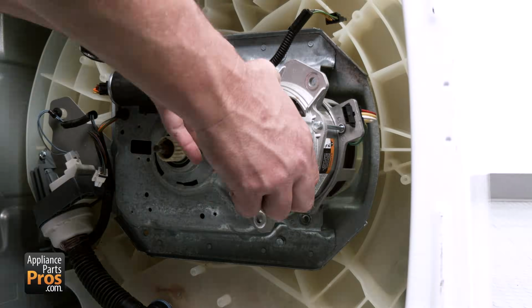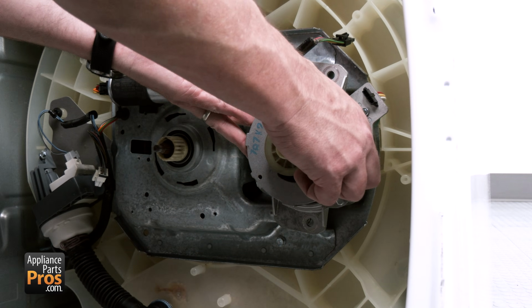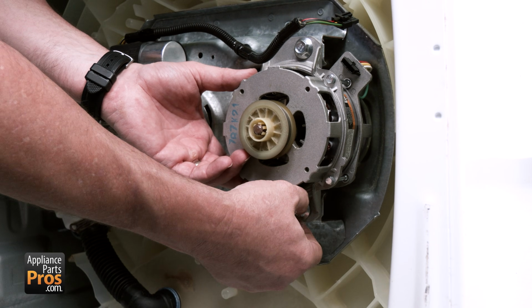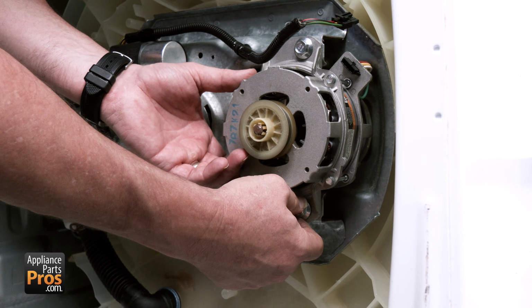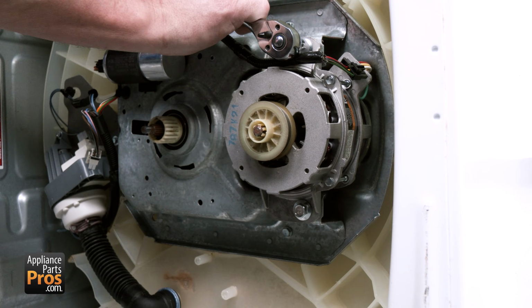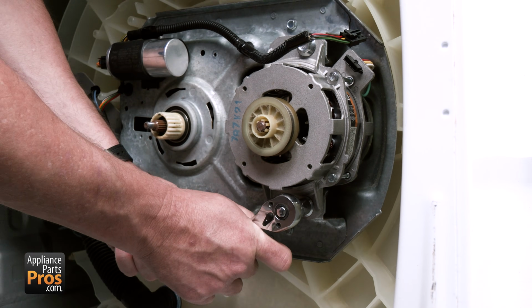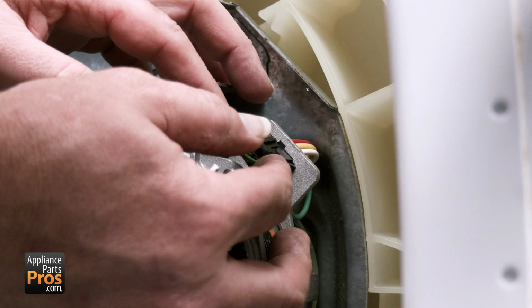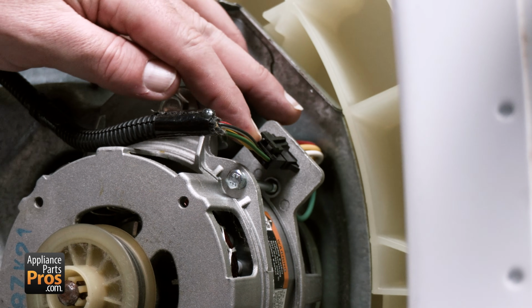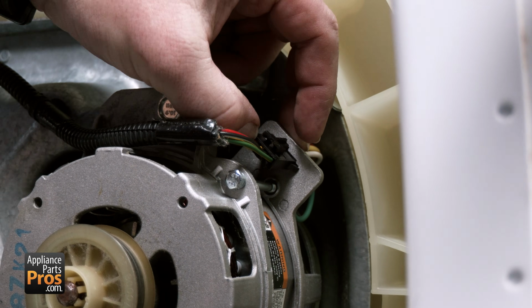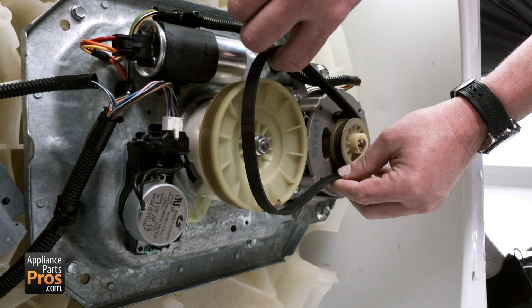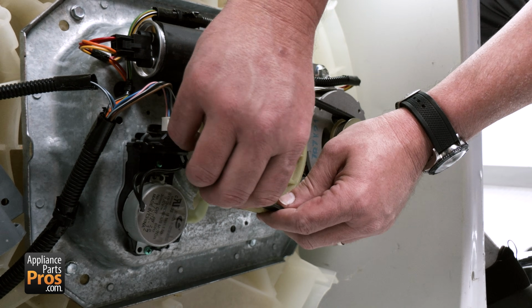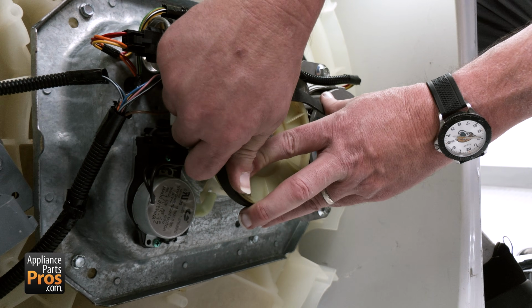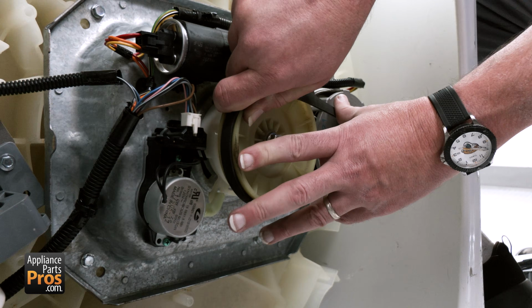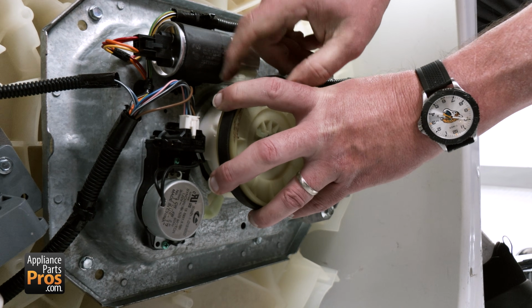Slide the new motor into the mounting bracket and reinstall the mounting bolts. Tighten them securely with your 13mm socket and ratchet. Reconnect the motor wiring harness, making sure all terminals are fully seated. Reinstall the drive belt onto the motor and splutch pulleys. Then rotate the pulley by hand to make sure that the belt is properly aligned and the splutch moves freely.